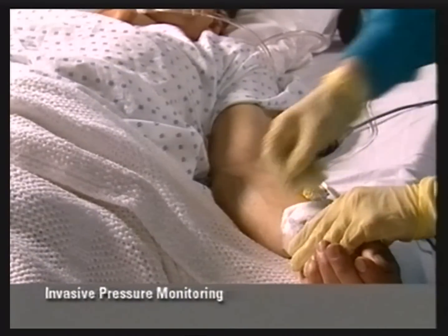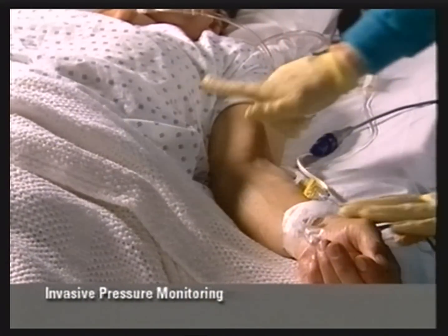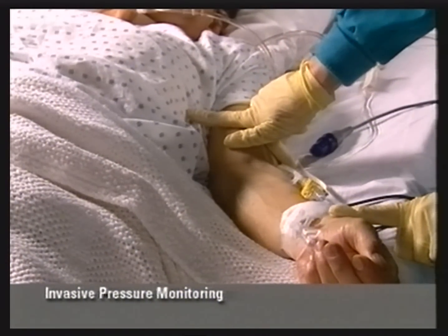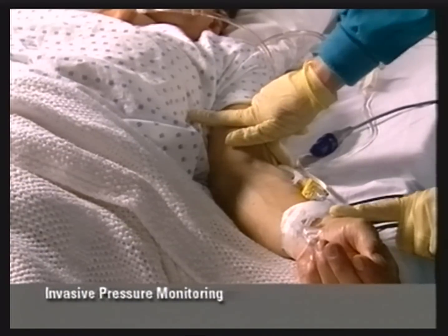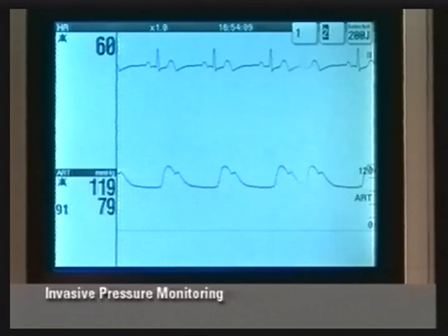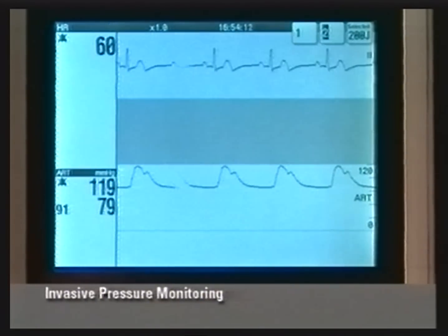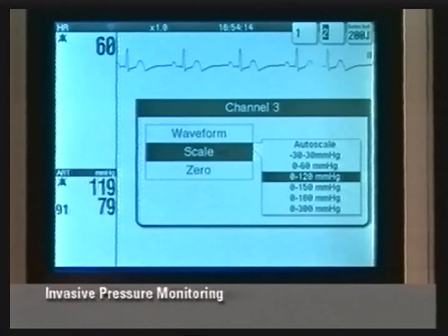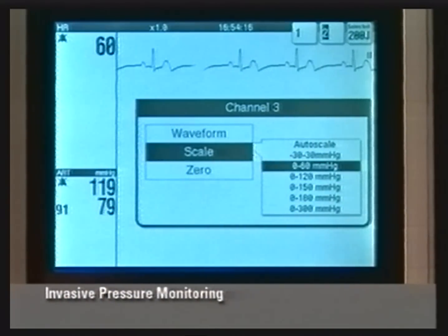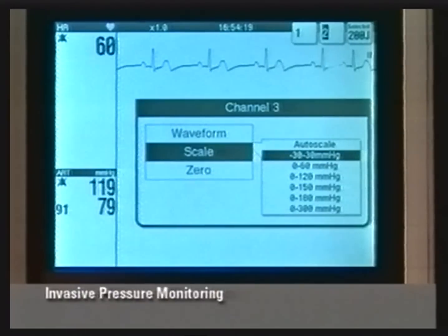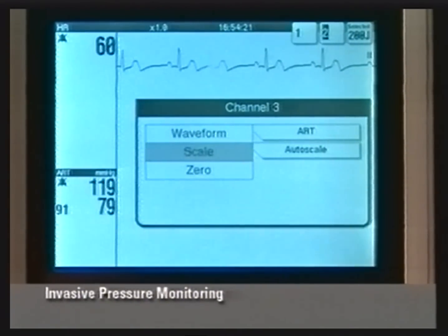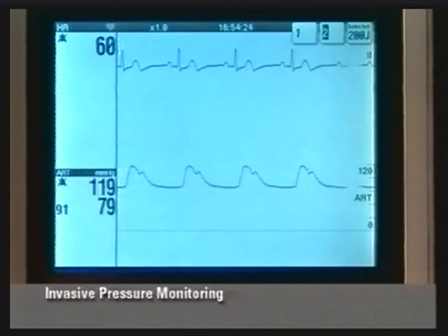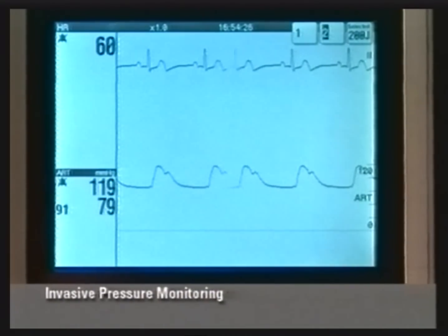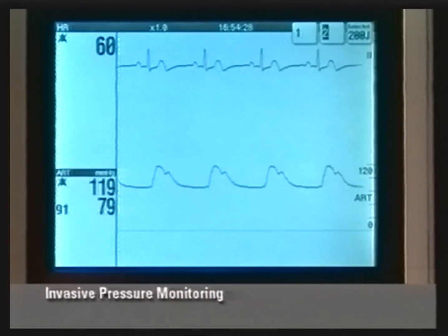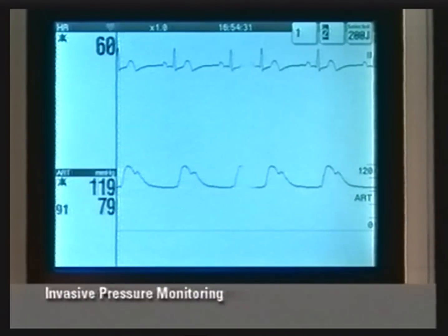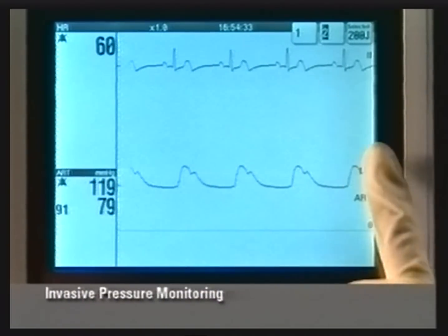Close the transducer stopcock. Be sure that the transducer is positioned at the patient's phlebostatic axis as a zero reference level. The patient's pressure waveform should be displayed. Pressures between -30 to +300 millimeters of mercury can be displayed, and 6 scales are available. When auto scale is selected, the monitor automatically selects the appropriate scale for the waveform based on the measured pressure. Once the waveform is on the display, confirm that the pressure waveform amplitude correlates with the digital readout.